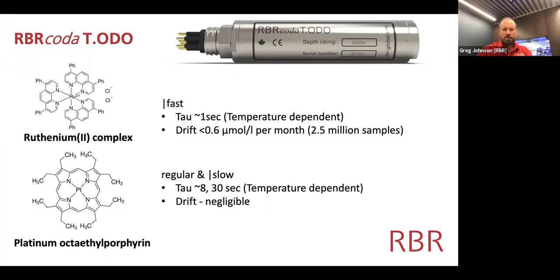In order to do the fast foil, we need a luminophore that is much more sensitive because we're going to illuminate it for a much shorter period of time, and we also need to be able to see all the way through it because we're not going to wait for the oxygen to diffuse through the foil, which is quite a slow process. So you'll see later on, I'll show you a photograph of the foil. The foils for the fast are almost transparent. They're very slightly tinged pink, as opposed to the regular foil, which is opaque.